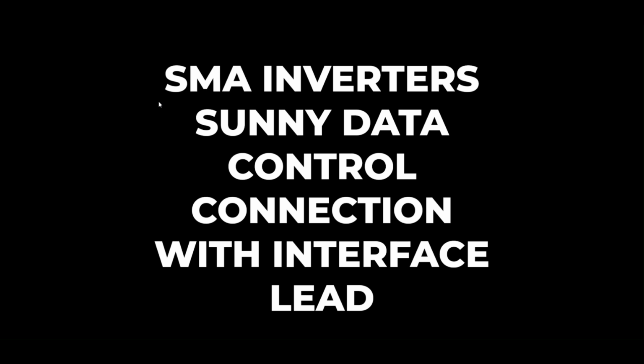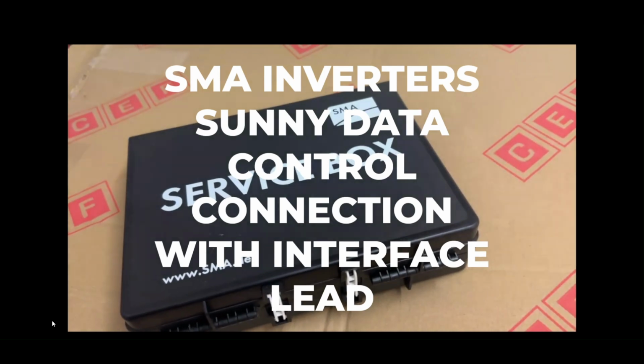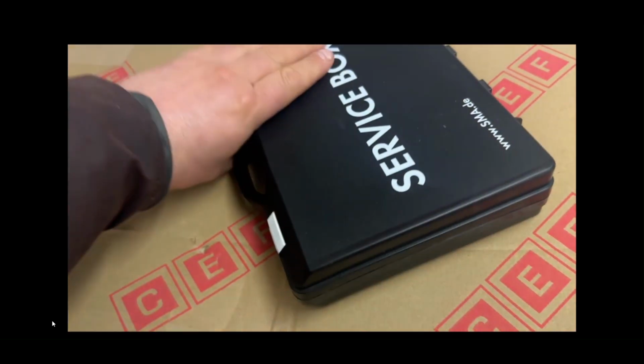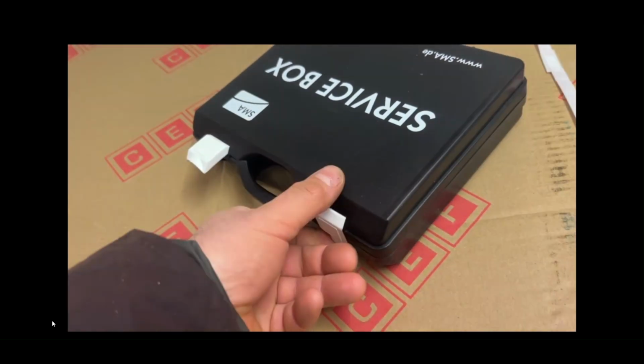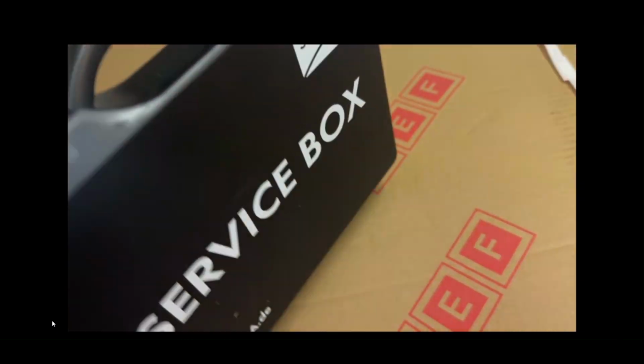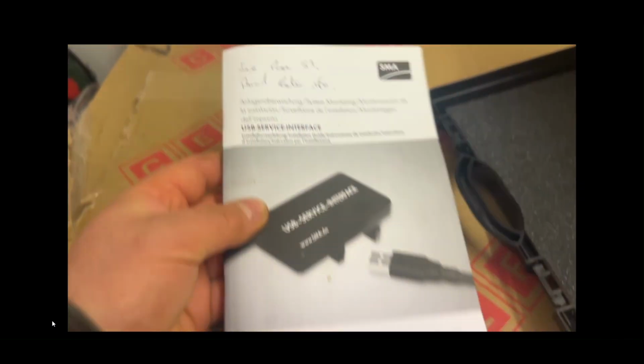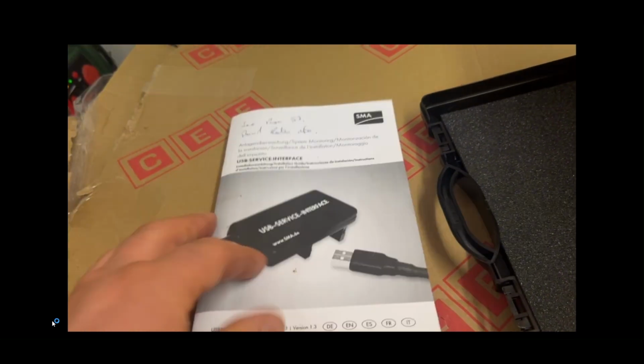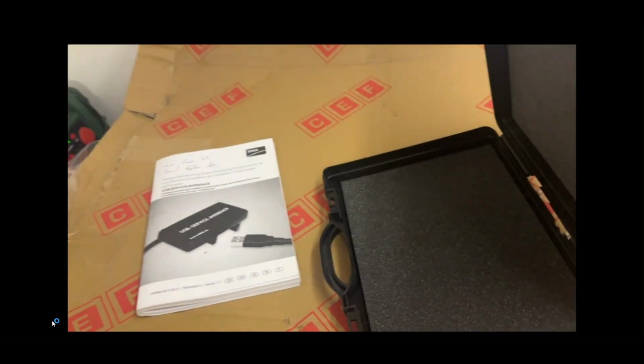Okay, it's a quick video on the SMA inverters, Sunny Data Control, using the interface. This is for the old style SMA inverters, not the new style. This is the interface box. Lead comes in, manual. I've written a quick note about page 53 because that's a baud rate setting that you always forget, and then you spend hours trying to figure out what's gone wrong.